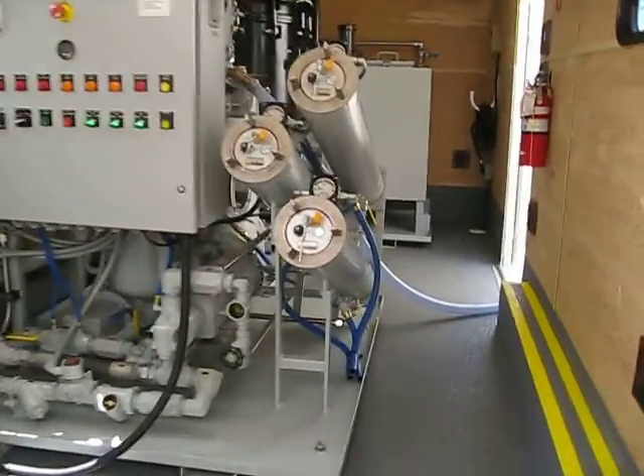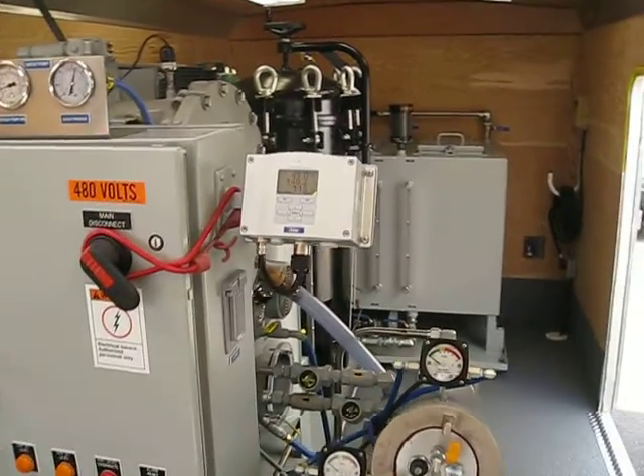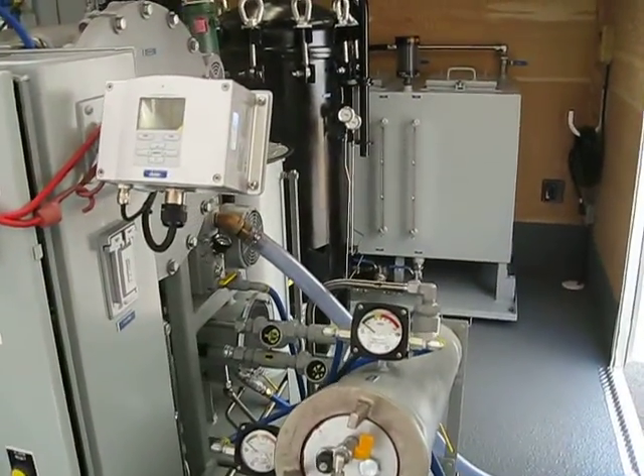It's got a double moisture monitor on it. We added water this morning, working away at 115 parts per million. We'll get that down to less than 10 very quickly.